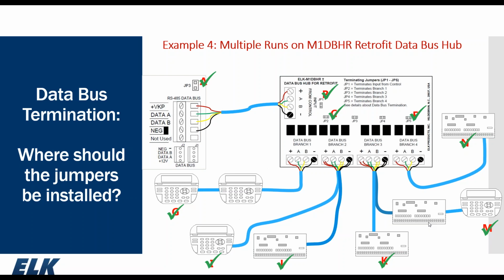Now that doesn't necessarily mean we're seeing the proper resistance. A and B could still be reversed and we would still not be able to enroll the devices. But it's just a quick and easy way for us to first eliminate maybe a broken wire. If you know the jumpers are in the right place, you're still reading 120 and your device won't enroll, it's very possible we could have a broken wire, a loose connection. If you read less than 60, we know we have too many jumpers, which can be a problem as well. So it's a quick and easy way to do a little troubleshooting on the M1 data bus.